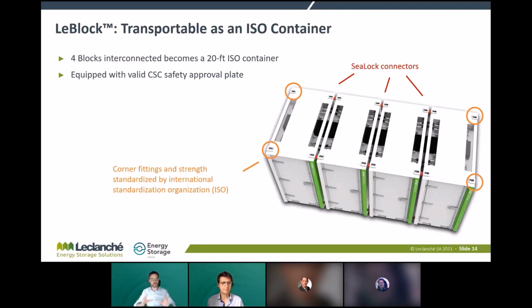We can handle those blocks, once connected, as standard shipping containers. Each block comes pre-equipped, pre-assembled, pre-wired, and pre-tested, and can be shipped as is, without additional enclosure, directly to the site. This is a huge improvement in logistics expenses, reduces the carbon footprint, and massively reduces installation times on site.